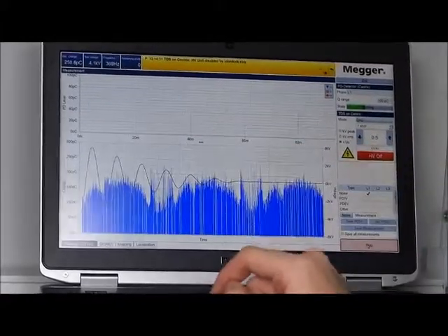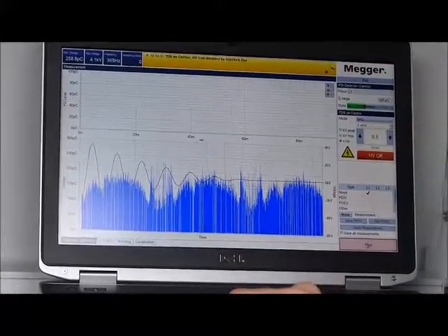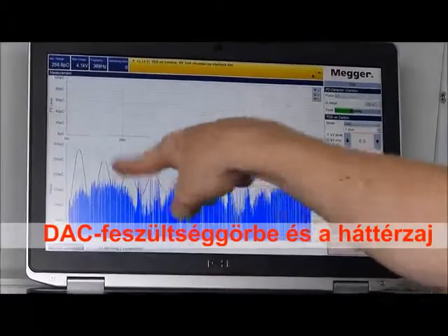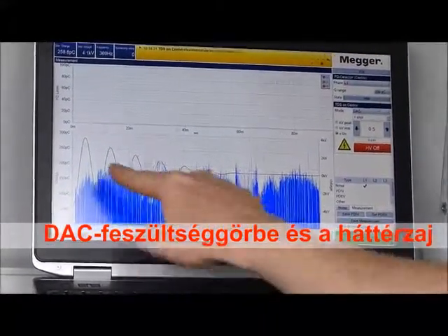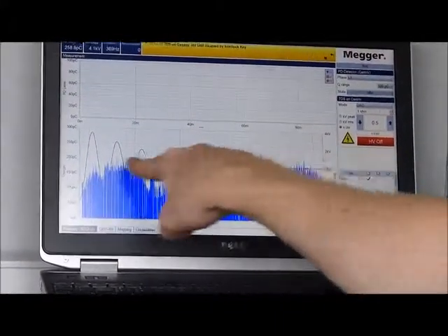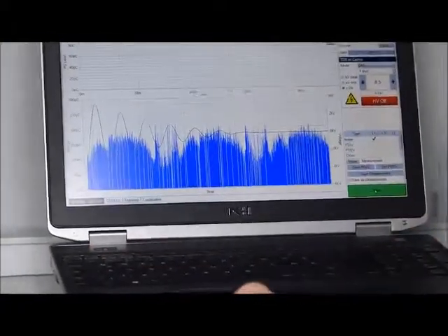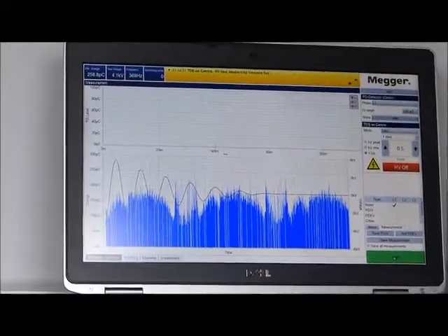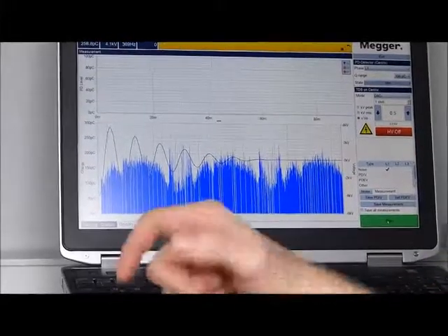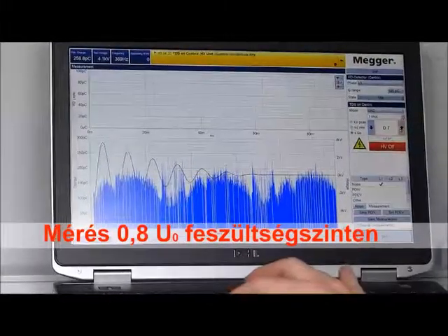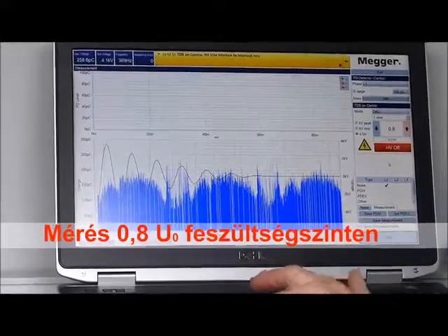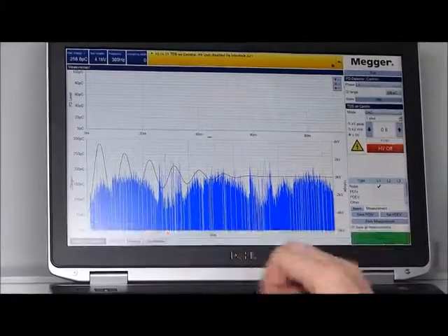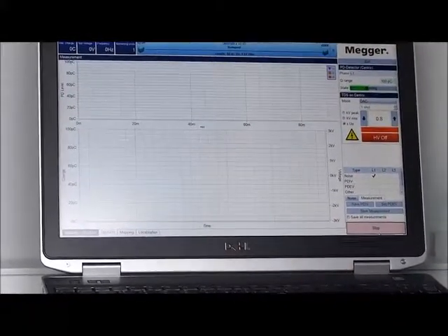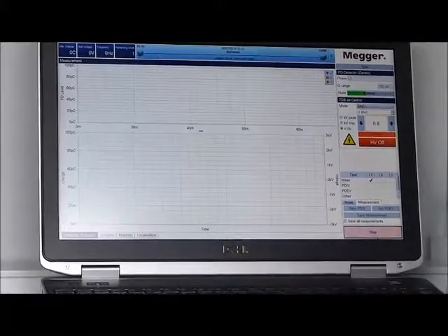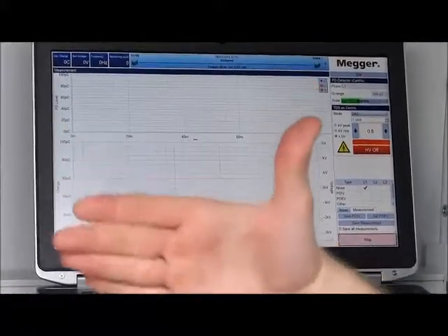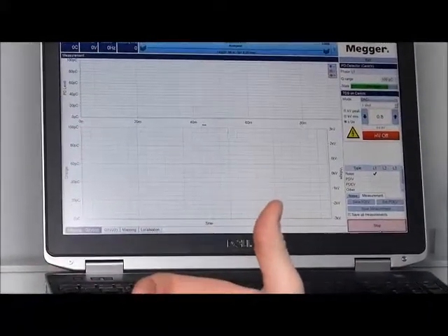Now it's transferring the data by the gray cable, and we see our damped AC voltage, and we see, okay, more or less, it's the same noise level, or the same partial discharge level than during the noise measurement. So we increase, let's say 0.8. Start. So this is the same operation like with the OWTS.